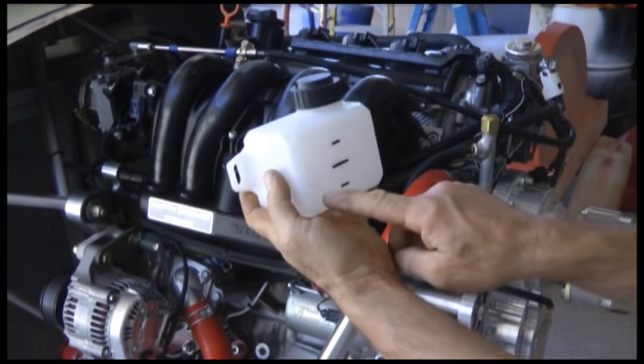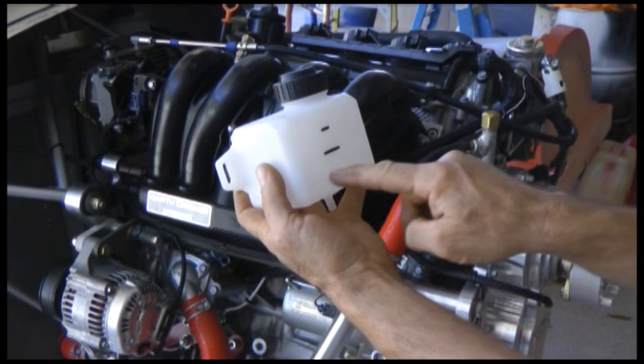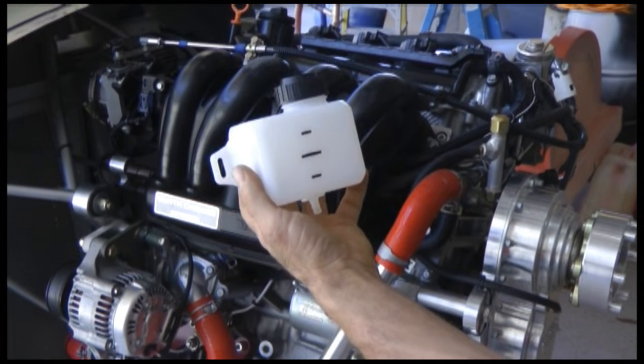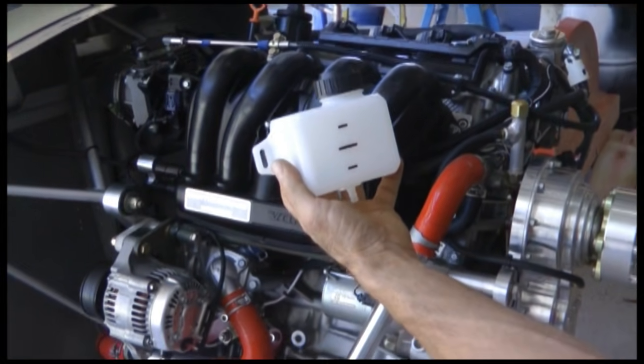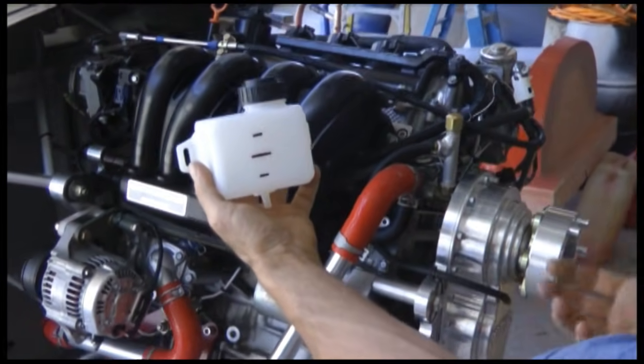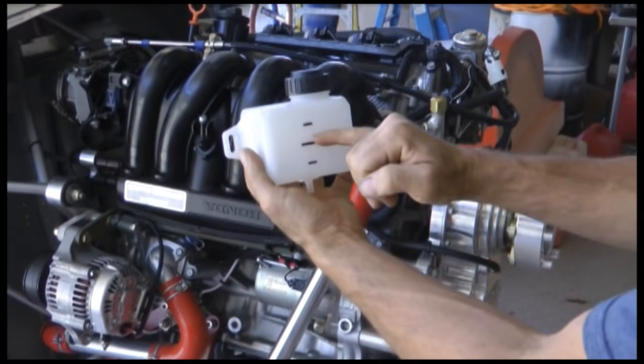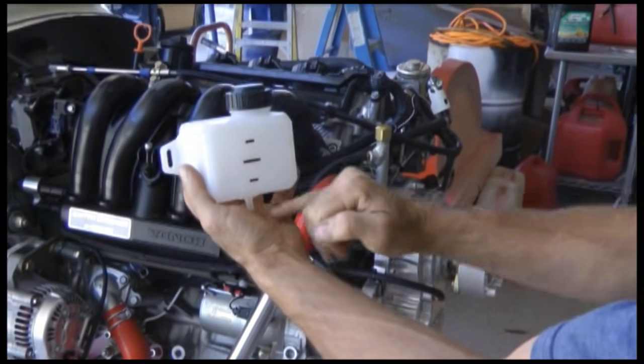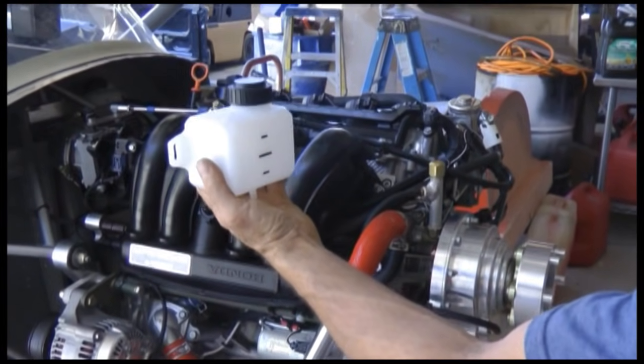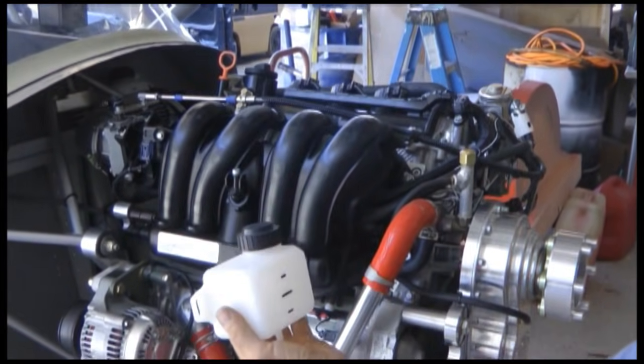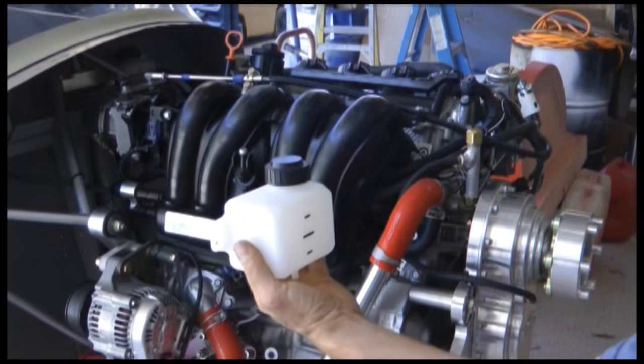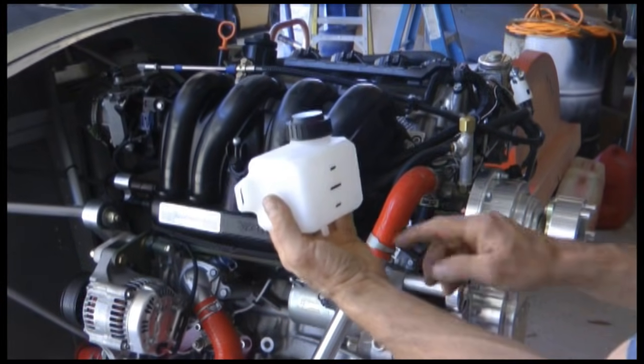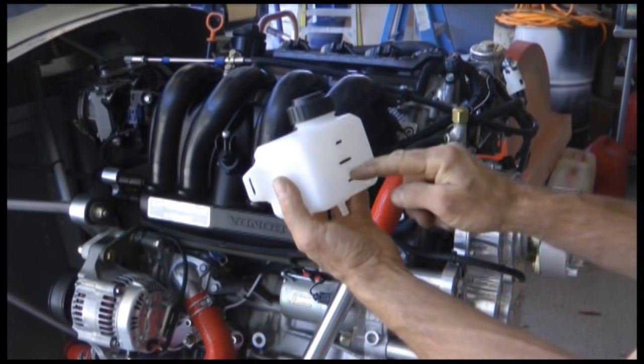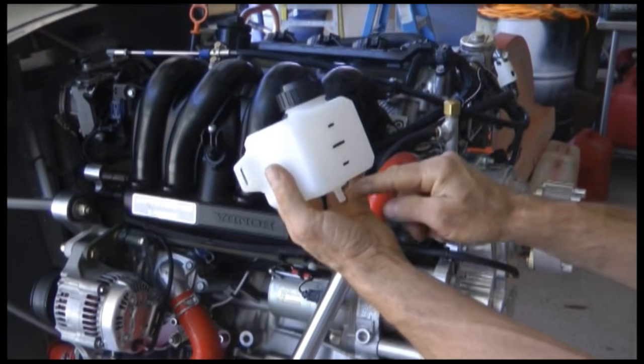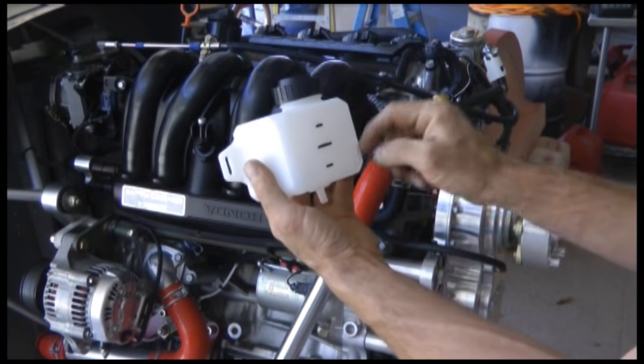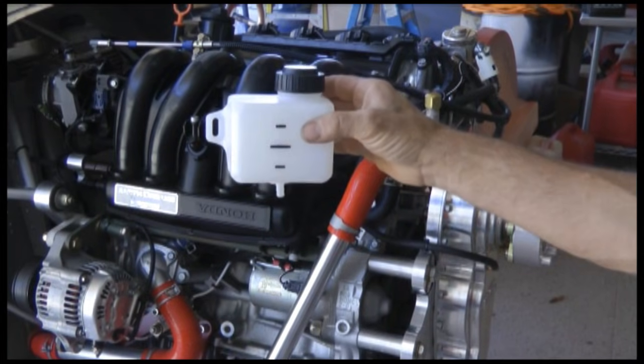You want to keep it at the first line after you have it all purged and the engine is cool. At operating temperature, you'll see it go to the middle line, maybe a little above. Mount it as high on the firewall as possible; if you have to mount it lower, it's not critical. The one thing that is critical is that it's always got fluid above it—you never want this to be empty, because then when the engine cools, it's going to be drawing air into the engine rather than coolant.